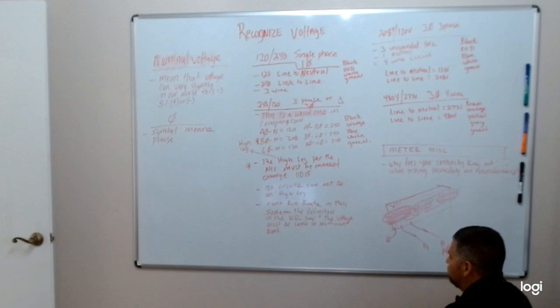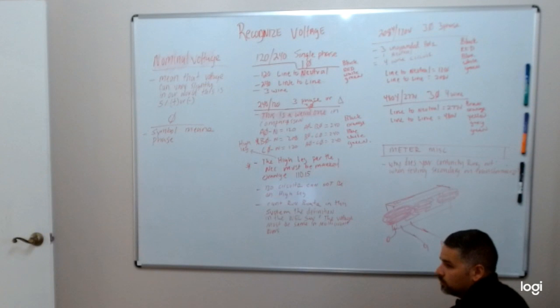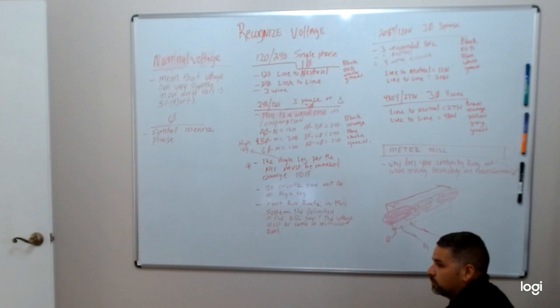Okay. So it's ringing out because your voltage coming into the transformer that you want to dumb down through the transformer is connected to your other side, which is kind of like a line load situation. Your line coming into the transformer and your load coming out of the transformer, because those are all connected. That's why it's ringing out?